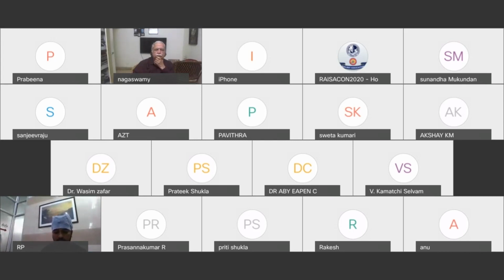The color coding of the cylinders, sir. Color coding is: oxygen has black with white shoulder; nitrous oxide has blue. Then the pin index safety system, sir. Oxygen has 2 and 5 pin index safety system. Nitrous oxide has 3 and 5.